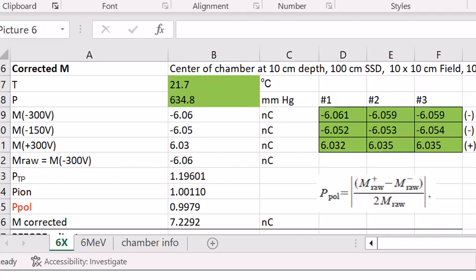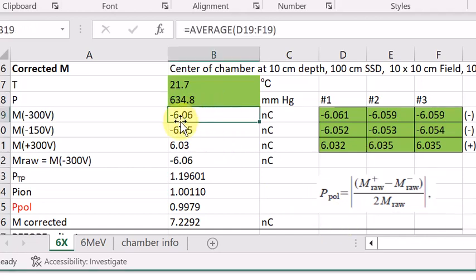So what it means is in our case ADCL calibrated our chamber at negative 300 volts. So our mraw reading is nothing but the reading when the chamber is operated at negative 300 volts. In our case which averaged to the negative 6.06 nanocoulomb when the chamber is biased at negative 300 volts.